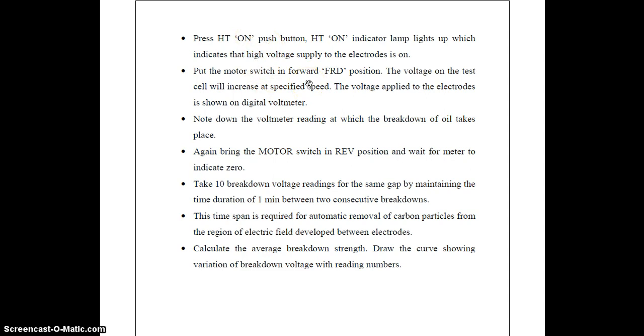The voltage on the test cell will increase at the specified speed. The voltage applied to the electrode is shown on the digital voltmeter. Note down the voltmeter reading at which breakdown of oil takes place. Again bring the motor switch to the reverse position and wait for the meter to indicate 0. Take 10 breakdown voltage readings for the same gap, maintaining a time duration of 1 minute between two consecutive breakdowns. This time span is required for automatic removal of carbon particles from the region of the electric field developed between the electrodes.